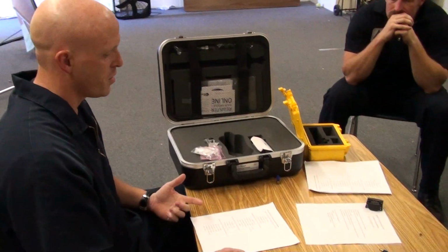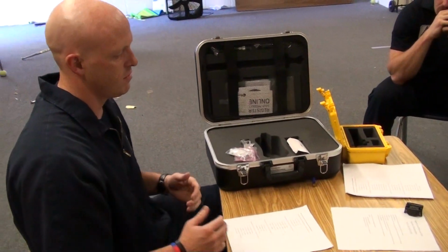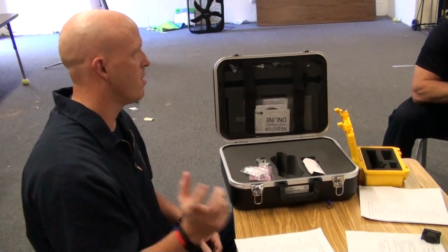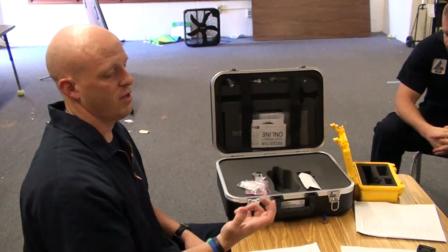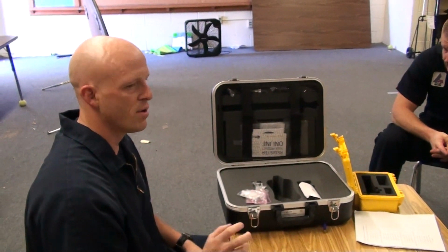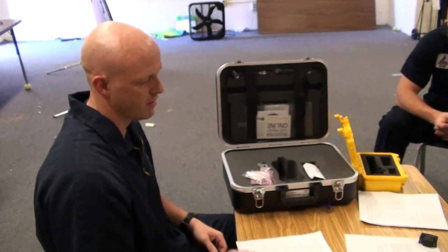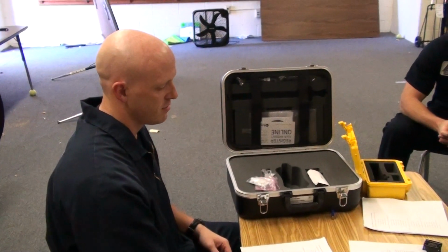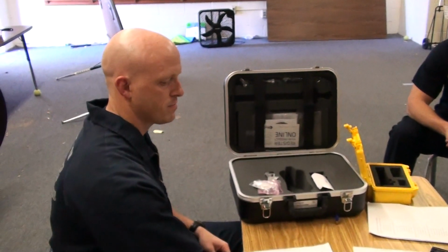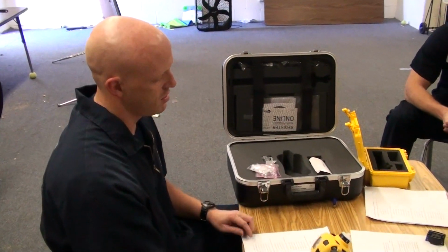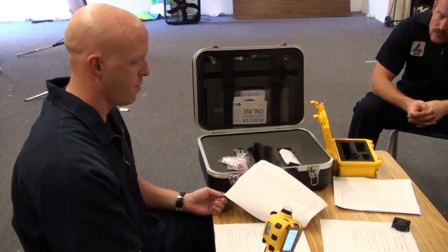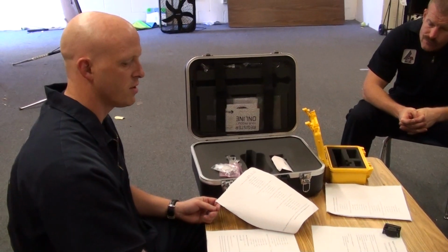These also have a response time. I put it on each one, which means you can't just run around through a building and come back and be like, oh, this is what readings it is. You may pick up something, but it's not going to be an accurate reading. Most of them are 30 to 15 seconds. However, ammonia is 60 seconds to pick up exactly right. Only ladder 5 has ammonia.